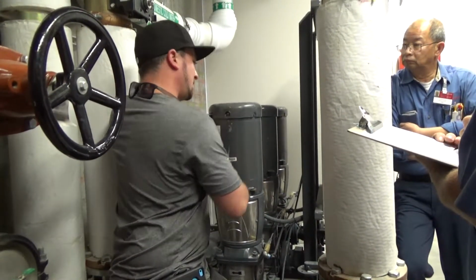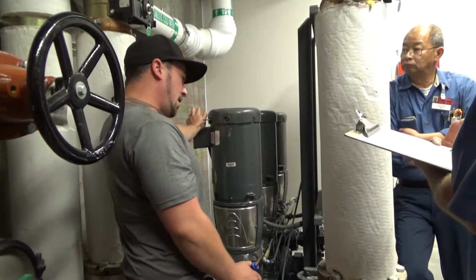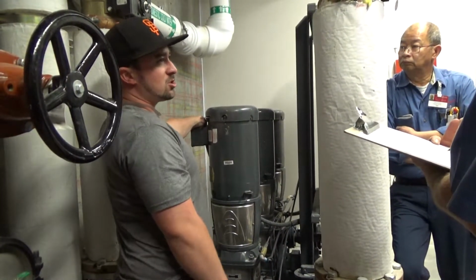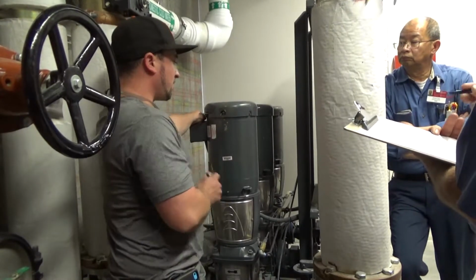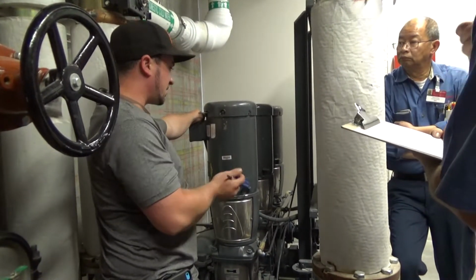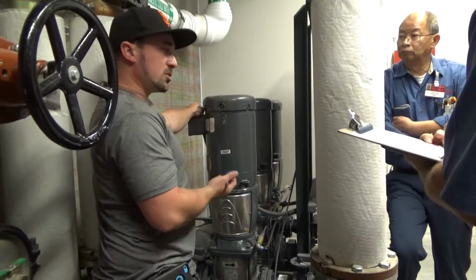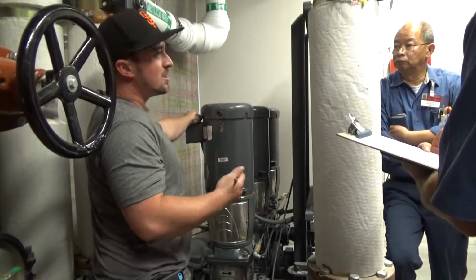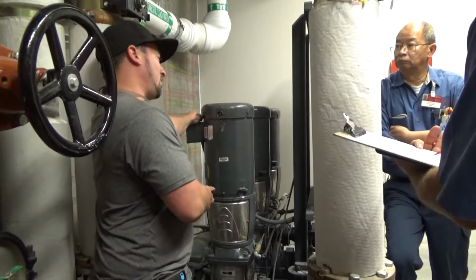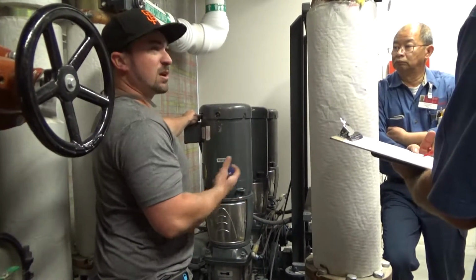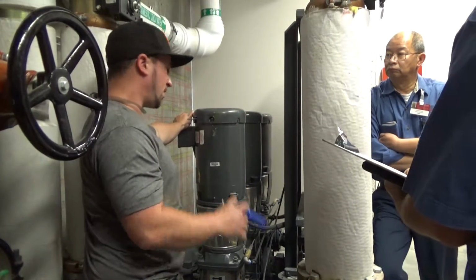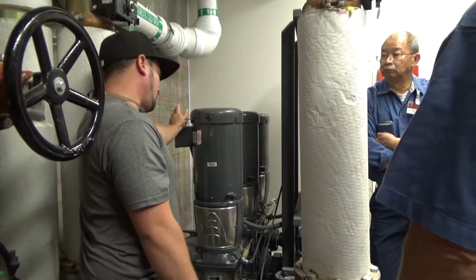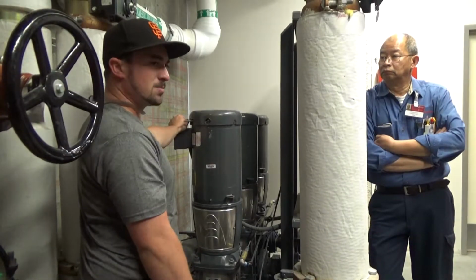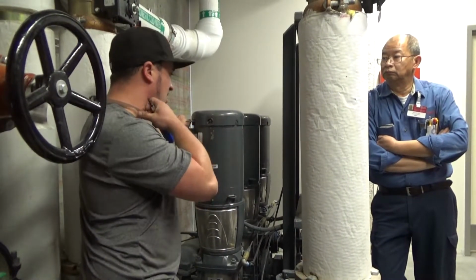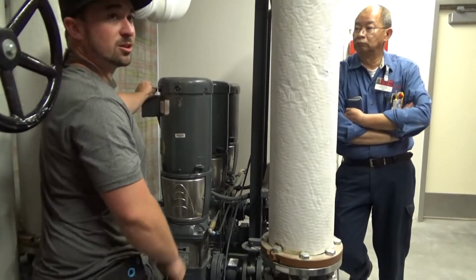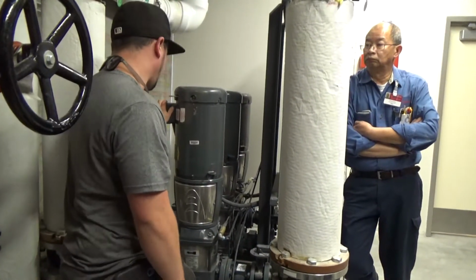But grease it depending on runtime. There should be a chart in there. It all depends on how much the pump runs and the environment that the pump's in. And that dictates how often you grease. So if you're in a really dry environment, the thing's running 24/7, you're going to grease a lot more than if the thing runs a couple hours a day or never runs and it's in a normal environment. So most of the time, once a year, a couple of pumps of grease, inboard, outboard, should be good enough, or just let it go until it starts squealing a little bit, do a couple pumps and go that way.